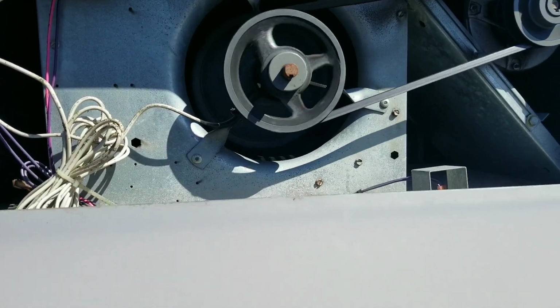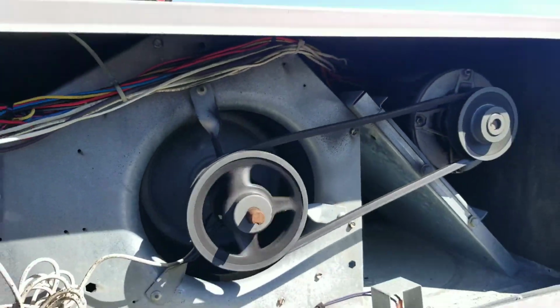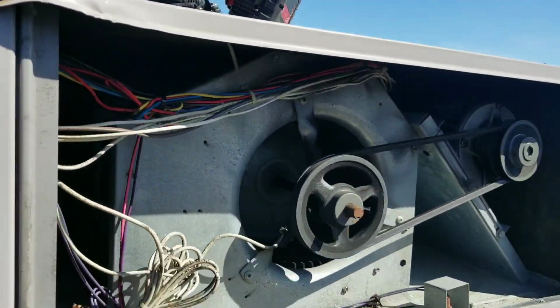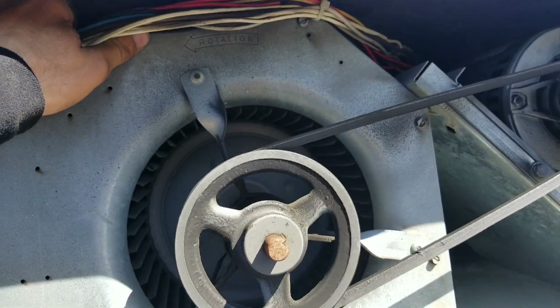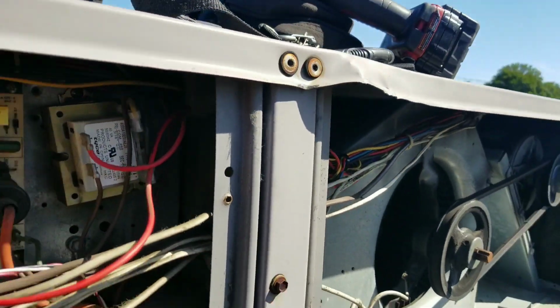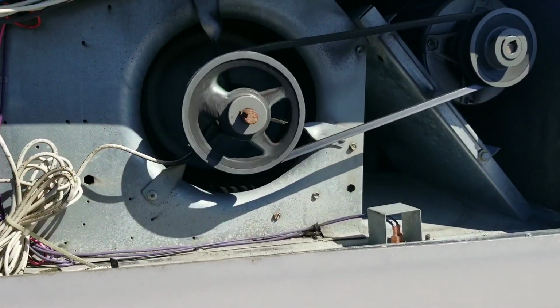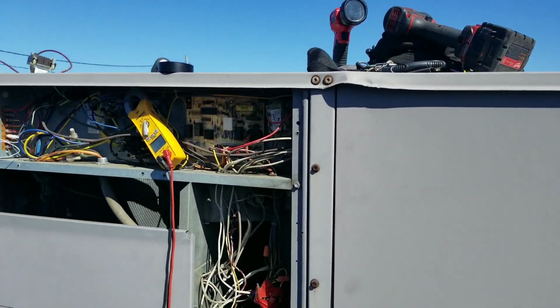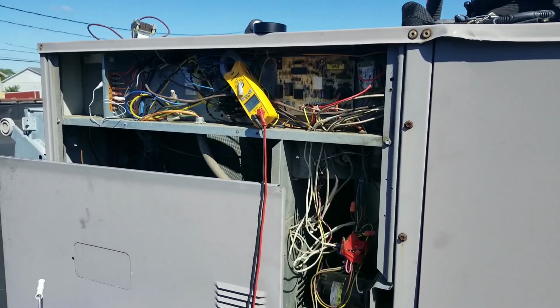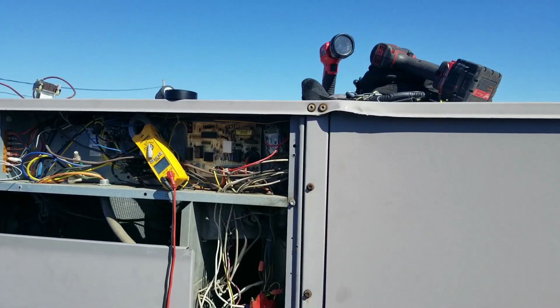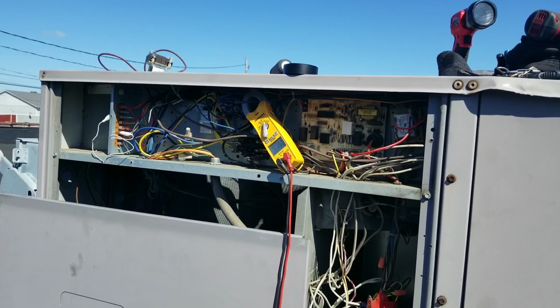Let's get this cover back on here. I checked the rotation on that. I didn't feel like it was pulling much. Let's see. I believe we're going the right direction, but I just want to be sure. Yep, we are. There's our arrow going that way. All right, we're good. False alarm. Now you'll notice that belt on that blower was kind of loose. I am going to replace that while I'm here. But first I want to make sure everything else is running the way it should. So let's let this go for a little bit, guys. See what our supply temperature turns out to be. And then we'll revisit this in just a few minutes.